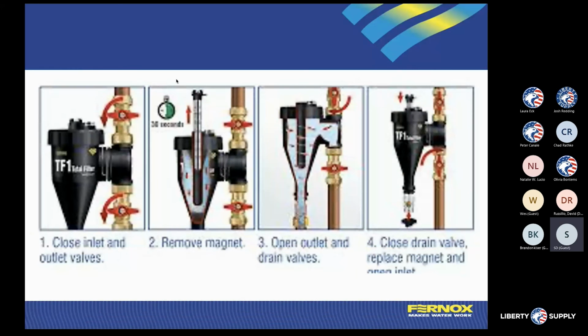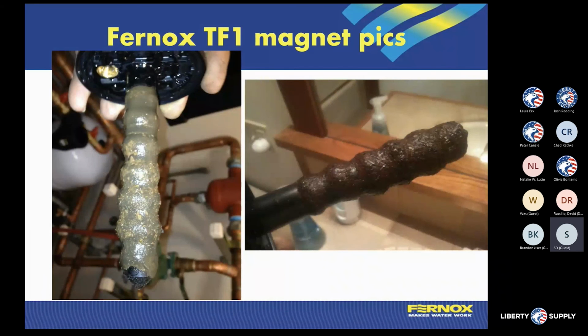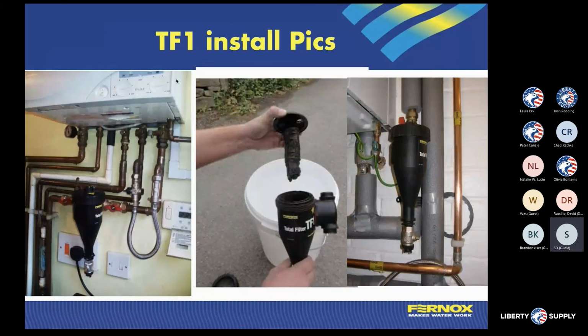So they kind of spin around, so you will get some sediment out, but that also gives us a great adhesion for removing the magnetism or removing the stainless steel or the steel products that have broken down or the black iron oxide. So typically when you pull that apart, you're going to see great buildup, just like we saw in the video. And this is just looking at some other pictures that we've gotten out of the field of getting some of that sludge and slime out of that system.